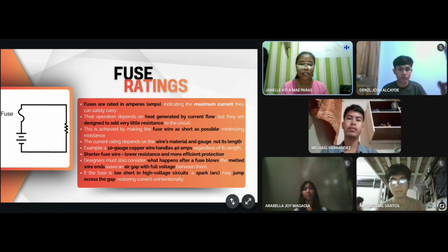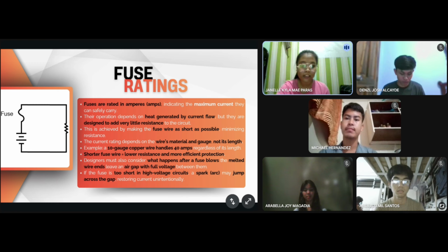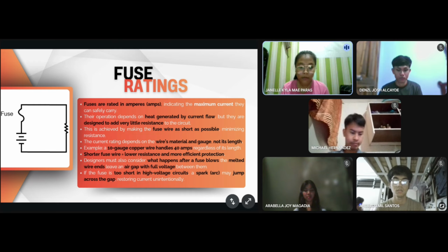Next is fuse ratings. Fuse ratings are measured in amperes, which indicate the maximum current a fuse can safely carry before it blows. The operation of a fuse depends on the heat generated by the current flow, but it is designed to add very little resistance to the circuit to maintain efficiency. This is achieved by making the fuse wire as short as possible to minimize resistance. The current rating of a fuse is determined by the wire's material and not its length. For example, a 10-gauge copper wire can handle 40 amperes regardless of how long it is.